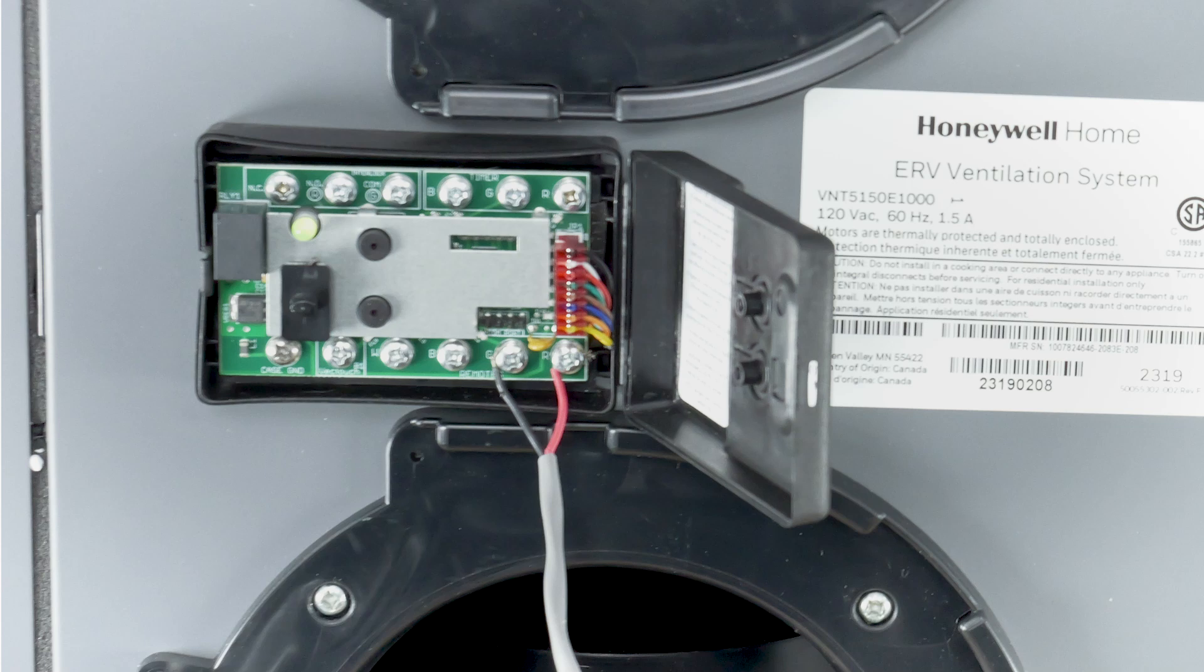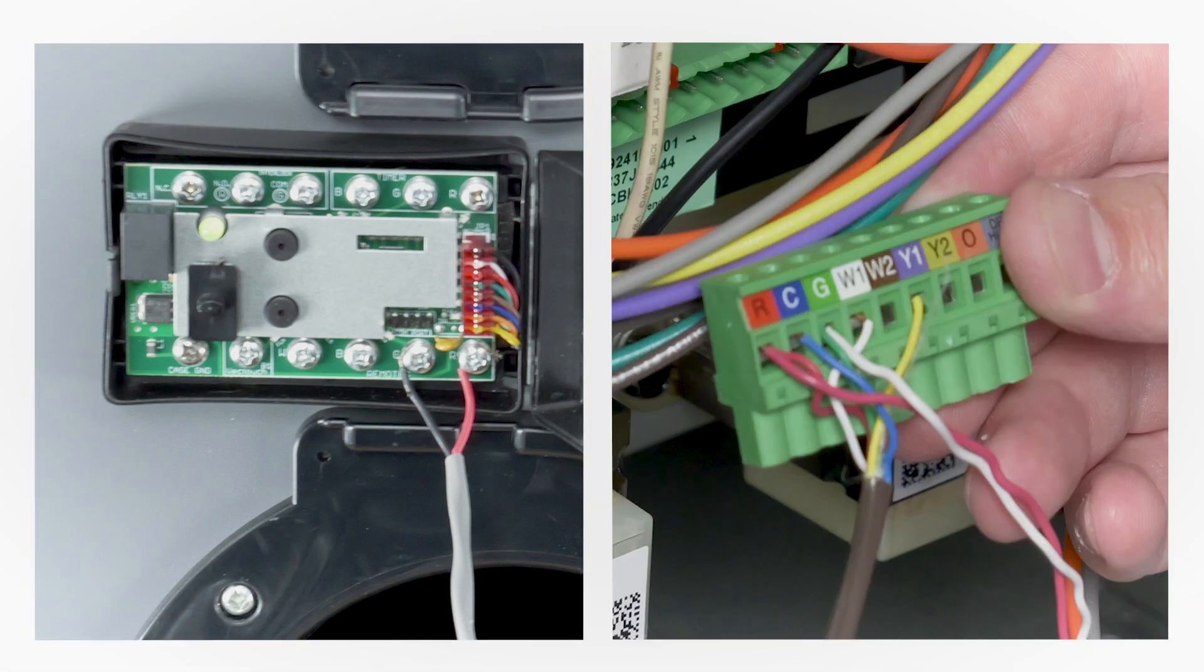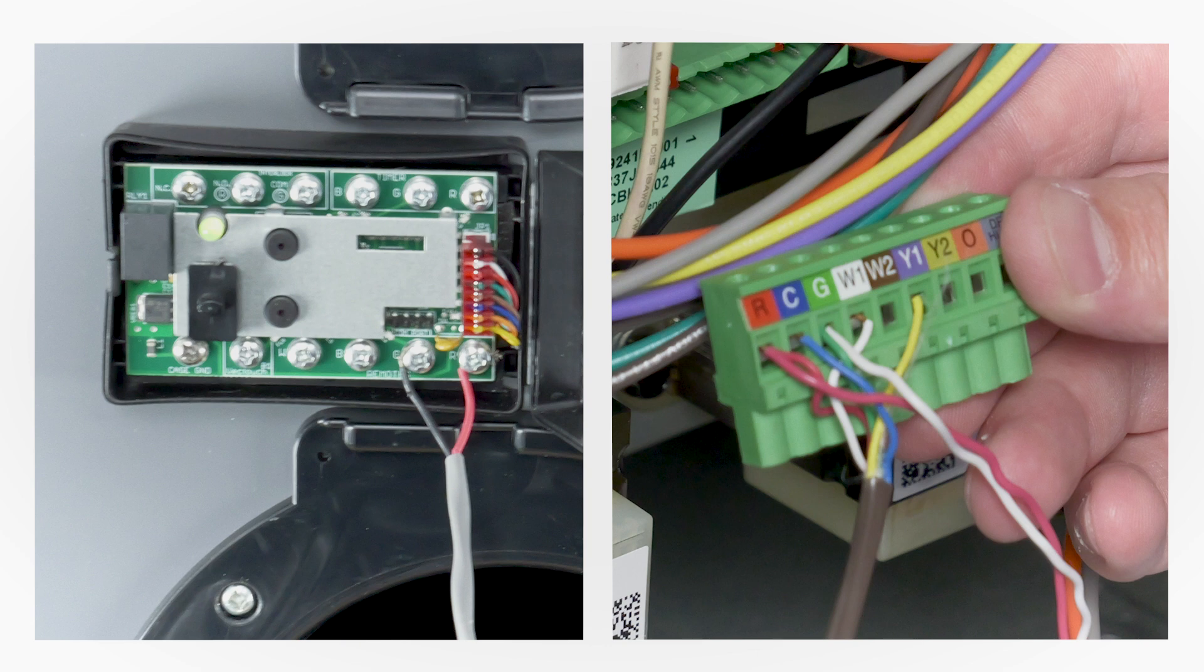Begin by wiring the interlock, NO, and COM terminals on the ventilator board directly to the R and G terminals at the furnace or air handler. These wires will be in parallel with R and G from the equipment side of the zone panel.